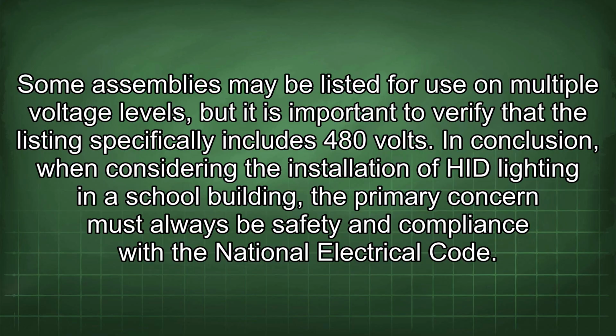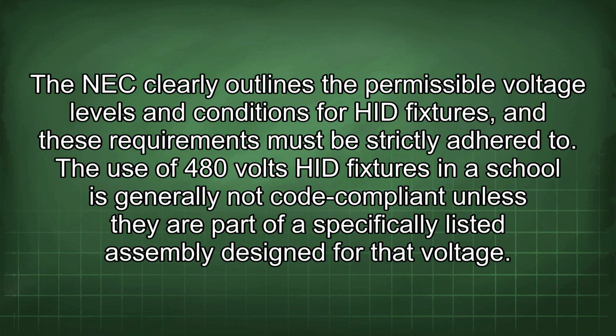In conclusion, when considering the installation of HID lighting in a school building, the primary concern must always be safety and compliance with the National Electrical Code. The NEC clearly outlines the permissible voltage levels and conditions for HID fixtures, and these requirements must be strictly adhered to. The use of 480-volt HID fixtures in a school is generally not code compliant unless they are part of a specifically listed assembly designed for that voltage.